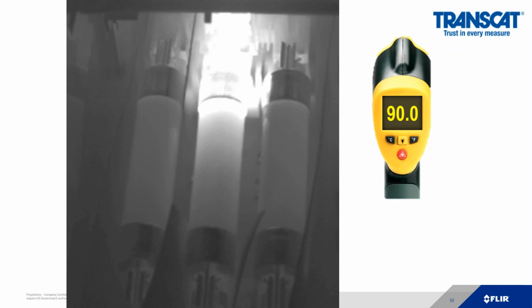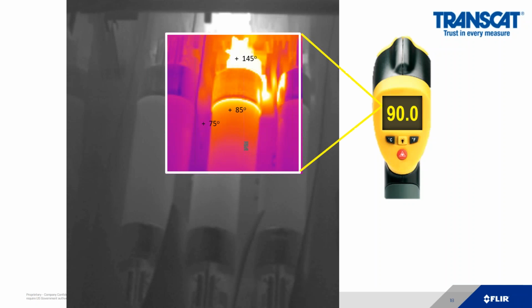So with these fuses, if I use a spot gun, I'm going to get a 90-degree temperature measurement. And the reason why is because I am looking at this picture, and if you see the 3 temperature measurements of 75 degrees, 85 degrees, and 145 degrees, you are averaging all those temperatures. So the spot gun has no ability to identify the hottest pixel because it's just 1 pixel, and that all becomes an average.